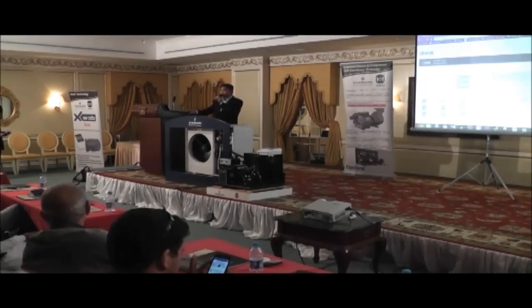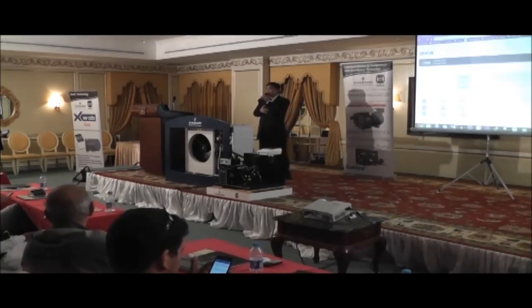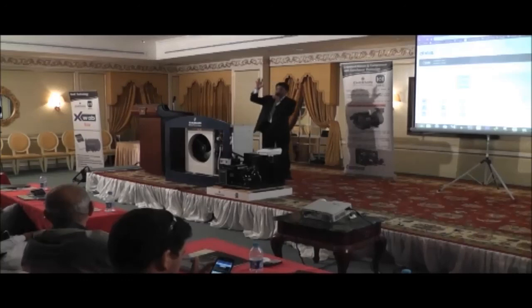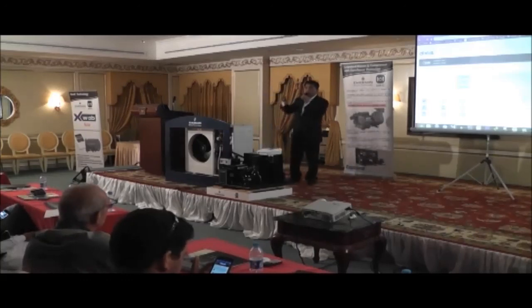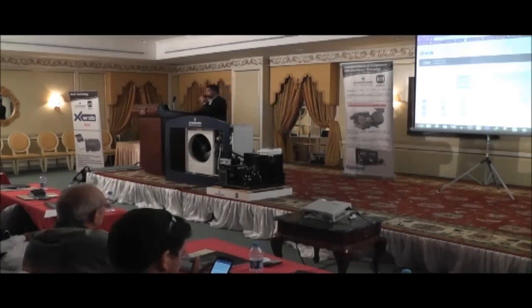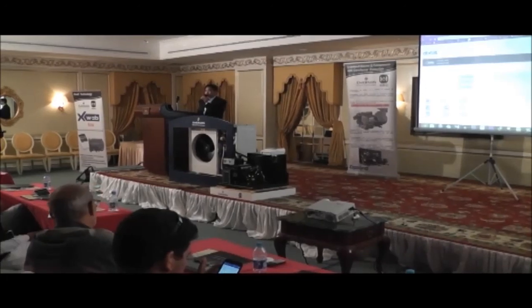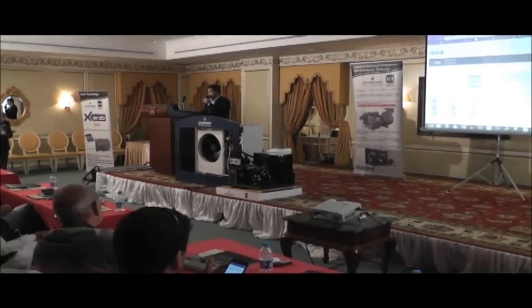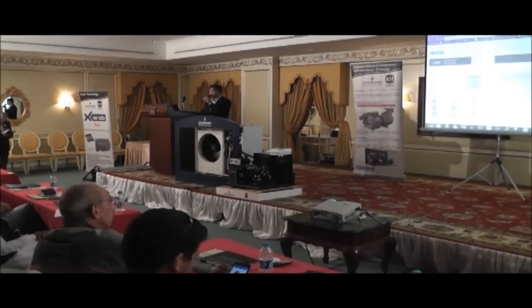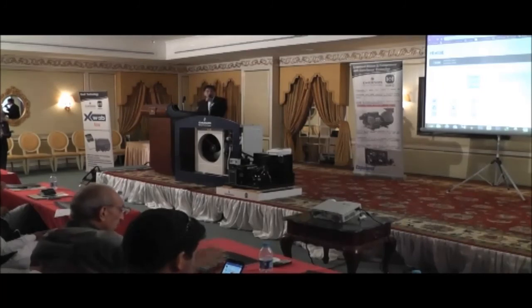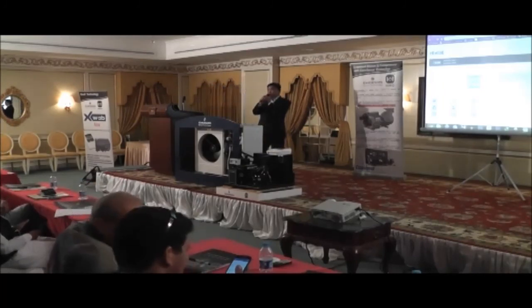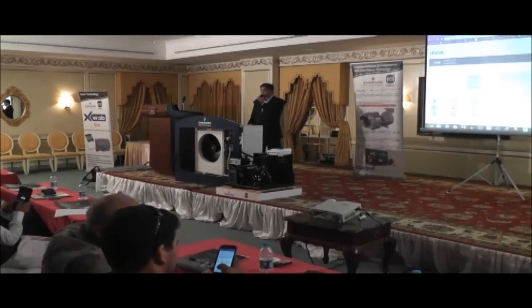what time, what day they made the changes to the controller. So no one can deny that they did not touch the instrument. Yes, somebody from that store made changes to the instrument, because on the server log you will see in each event the date, the time, and the activity. For example, modified parameter, it will show you modified parameter. So somebody played with the parameter. And then there are so many other capabilities of the X-Web. Not only to monitor the alarm, but you can also do the controlling, remote monitoring, remote controlling.